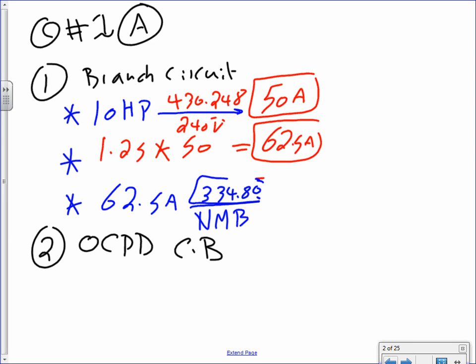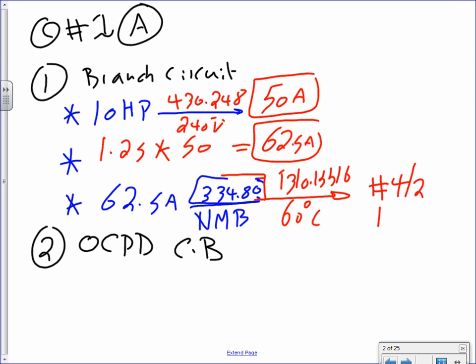All right, then I take the 62.5 to 334.80 NM cable, and then from there, you go to table 310.15(B)(16) under the 60-degree column. Anybody know why we're going under the 60-degree column? Because it's Romex, right? Romex is the 60-degree column. When you go there, guys, you are going to find you need the following. You need a 4-2 NM cable.